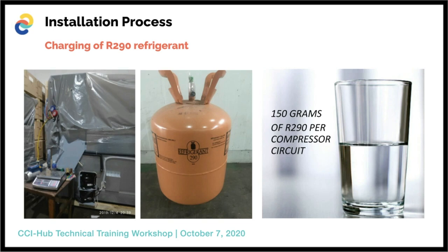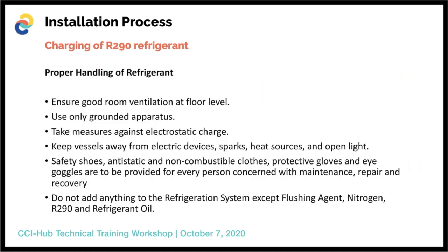And you can see also in the pictures the R290 5 kilogram cylinder tank. You can see also a half glass of water, just a little comparison of what 150 grams looks like in the system. And the next installation process is proper handling of refrigerant. The first is to ensure good ventilation at floor level.